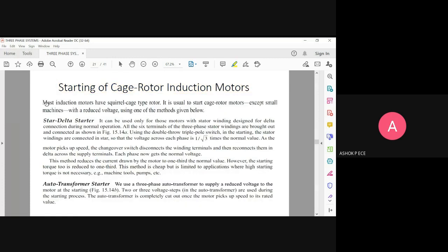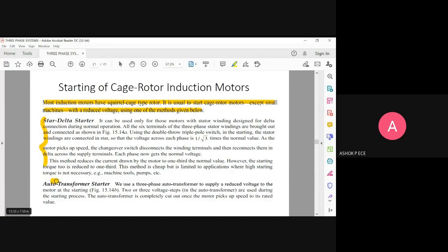For squirrel cage induction motors, it is usual to start with a reduced voltage. Starting with a low voltage can be accomplished using a star-delta starter. In a star-delta starter, the stator is designed for delta connection during normal operation, so you are going to use stator winding with delta connection for normal operation.